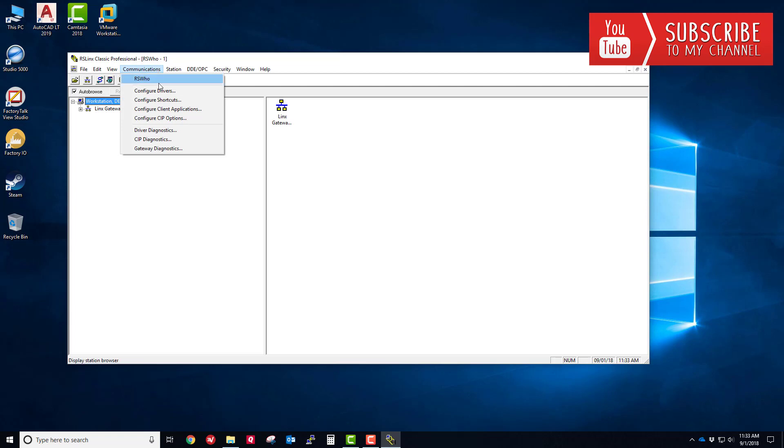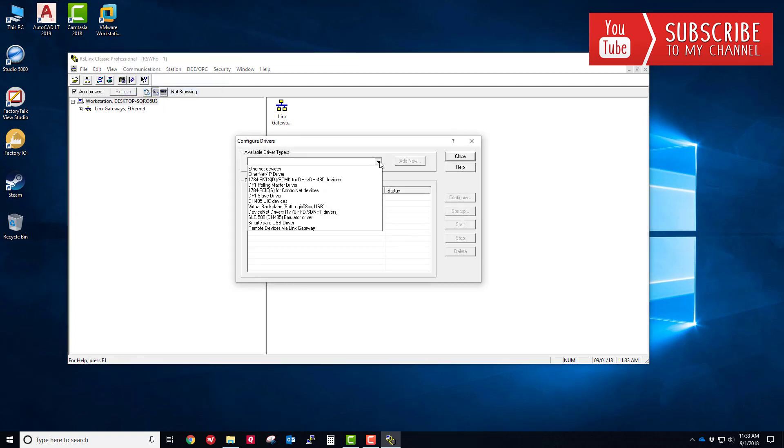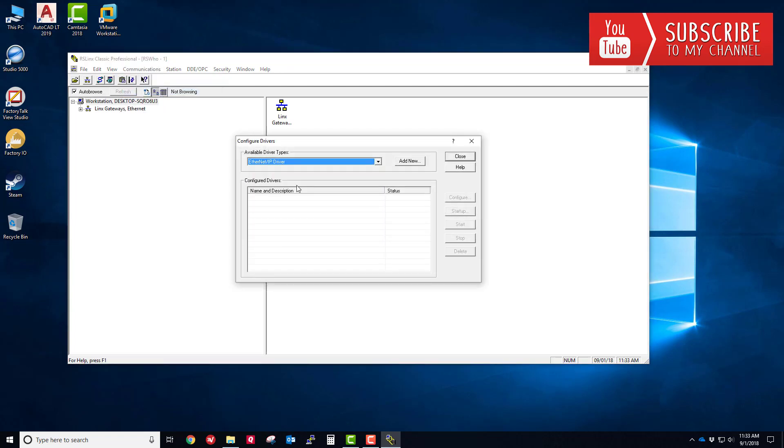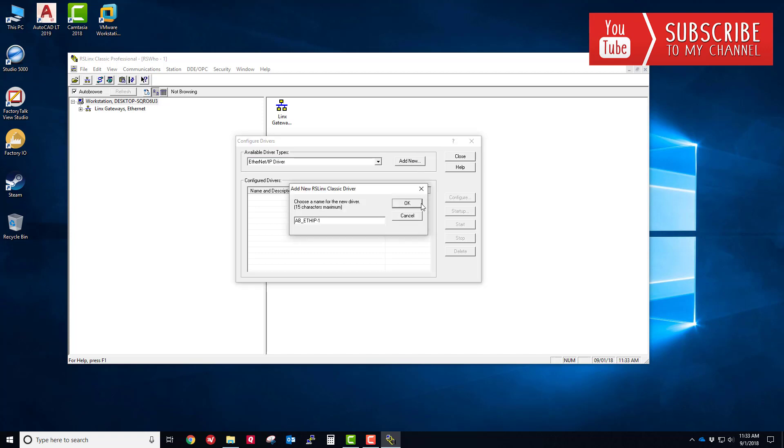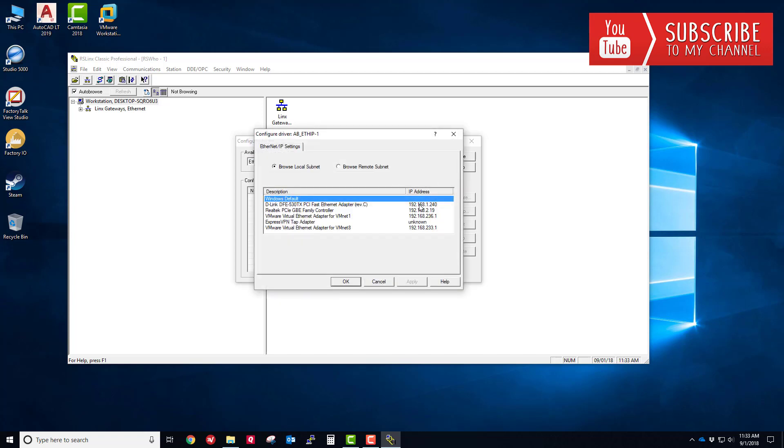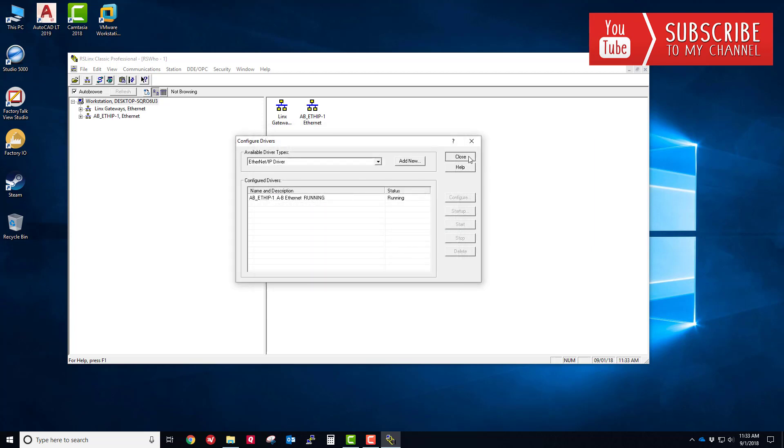I'm going to go to communications, configure drivers, and select the ethernet IP driver and click add new. Notice I have a few different NIC network interface cards in this machine as well as some virtual adapters because I run VMware. However, the physical NIC connected to that ethernet bridge is this one at 192.168.1.240. That's the local address of the NIC card I'm going to use to talk to that ethernet bridge, route through it, and get to my processor to downgrade the firmware. I'm going to click apply, OK, and close.